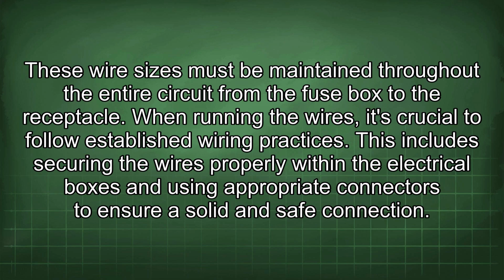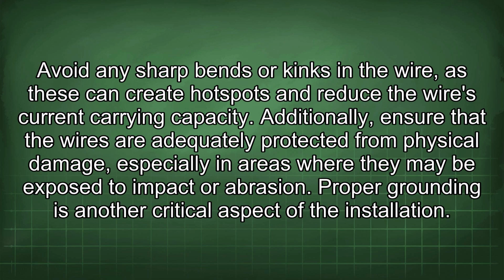receptacle. When running the wires, it's crucial to follow established wiring practices. This includes securing the wires properly within the electrical boxes and using appropriate connectors to ensure a solid and safe connection. Avoid any sharp bends or kinks in the wire, as these can create hotspots and reduce the wire's current carrying capacity. Additionally, ensure that the wires are adequately protected from physical damage, especially in areas where they may be exposed to impact or abrasion.